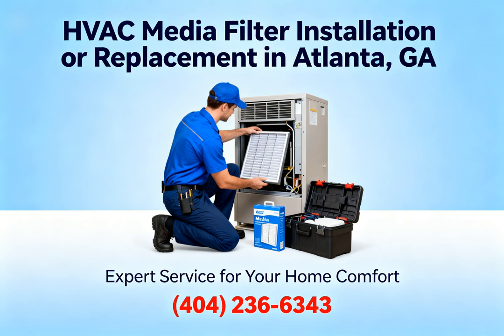And the most critical part of that custom housing installation involves the fluid dynamics of how air actually behaves, right? Because the sources highlight a major pitfall called bypass air. Bypass air is the enemy of a good HVAC system, because air is incredibly lazy. It will always take the path of absolute least resistance. Fluid dynamics dictate that air will not push through a dense, highly restrictive medium if there is an alternative route. If the custom housing cabinet isn't perfectly sealed, if there is even a millimeter of a gap between the filter frame and the sheet metal, the air just shoots right through the gap.